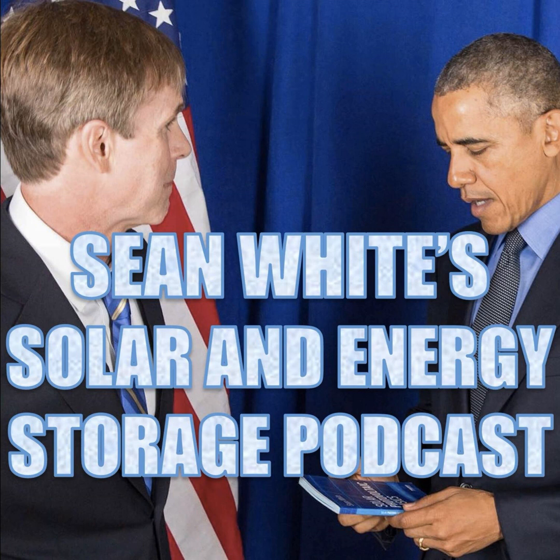Okay, now we have finished Chapter 4. Many people also think that storage batteries should not be in Chapter 4, equipment for general use. It should probably be in Chapter 6, special equipment. That's where we see photovoltaic systems. But it was brought there back in the days of Thomas Edison, where everything was DC, some will say. So it's just a relic that we can't seem to get rid of. That's Article 480, storage batteries. And it leads to a lot of arguments over people trying to apply 706 and 480 at the same time, and they contradict each other. And that's just the code. The code contradicts itself. It's not perfect like we are.